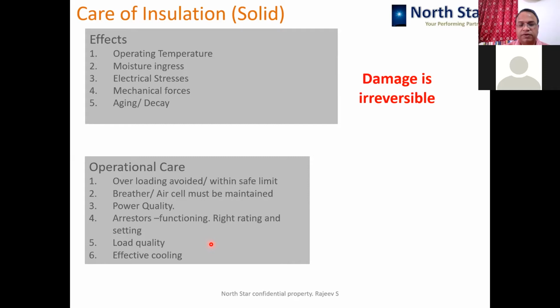Load quality as well as power quality we talked about, and effective cooling. Many times we see that transformers are put in such a situation where sufficient airflow is not there, or if fans are provided, the fans are not working properly, or the control circuit has some issues, or the settings are not right, such as the OTI and WTI settings which are supposed to switch on the fans at a particular load. All these factors affect the cooling of the transformer, and as a result we run the transformer at a higher temperature, and higher temperature definitely affects the solid insulation.